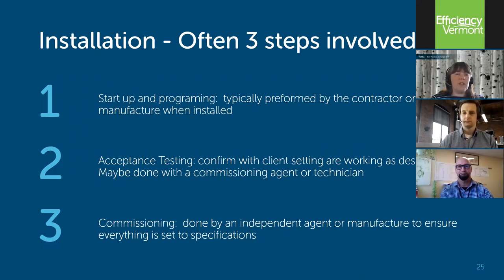When going through installation, initial startup and programming, we often go through 3 steps. We encourage a startup and programming meeting, talking with the contractor and manufacturer about how these will be installed. Then after everything's installed, get acceptance testing to make sure everything's working well and the client's happy, maybe with a commissioning agent walking through at the same time, confirming the install is done as we said.